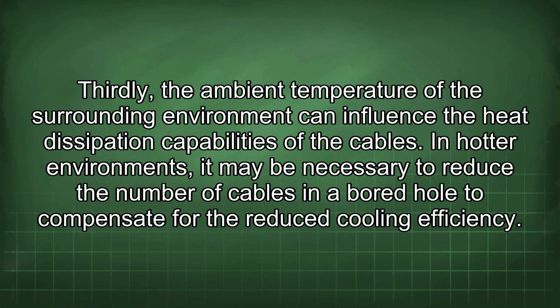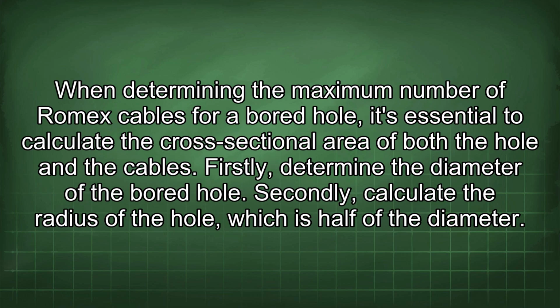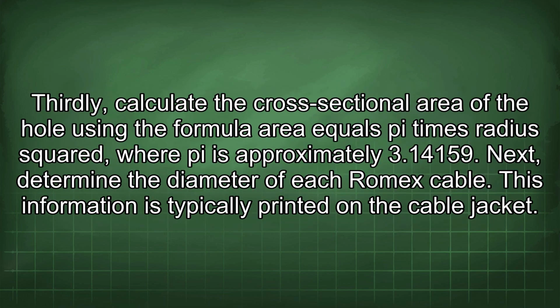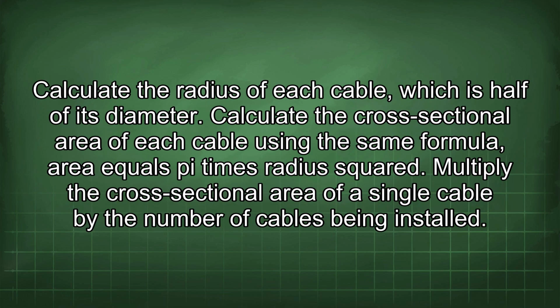the reduced cooling efficiency. When determining the maximum number of Romex cables for a bored hole, it's essential to calculate the cross-sectional area of both the hole and the cables. Firstly, determine the diameter of the bored hole. Secondly, calculate the radius of the hole, which is half of the diameter. Thirdly, calculate the cross-sectional area of the hole using the formula area equals pi times radius squared, where pi is approximately 3.14159. Next, determine the diameter of each Romex cable. This information is typically printed on the cable jacket. Calculate the radius of each cable, which is half of its diameter. Calculate the cross-sectional area of each cable using the same formula, area equals pi times radius squared.